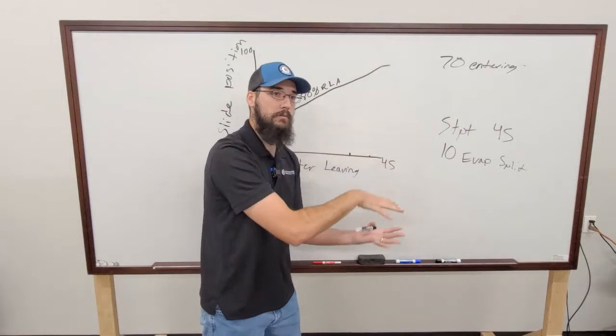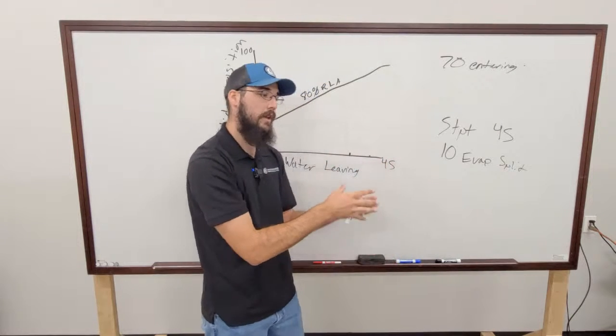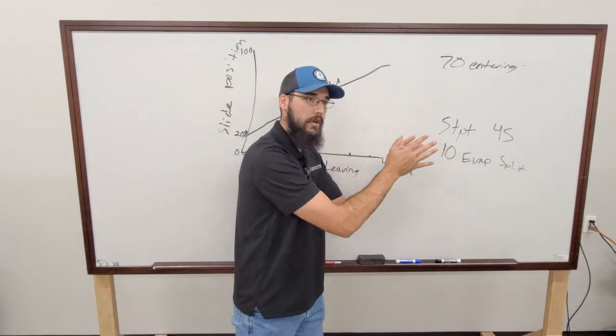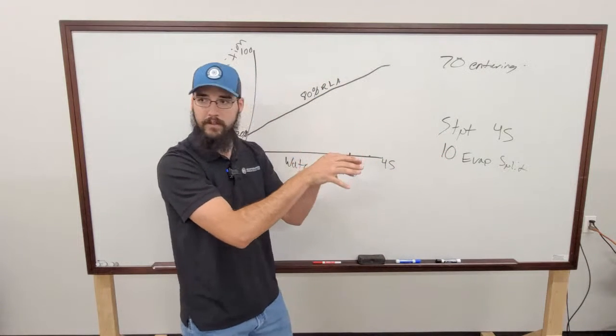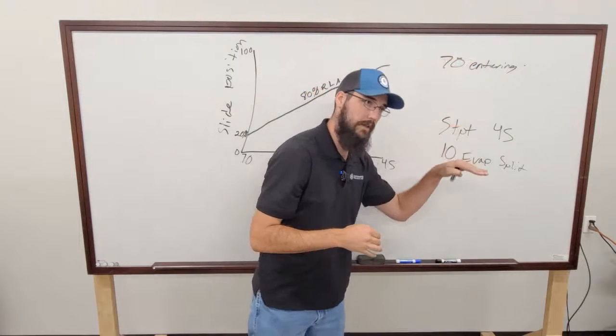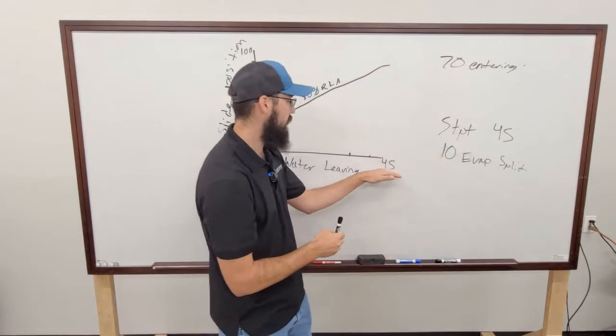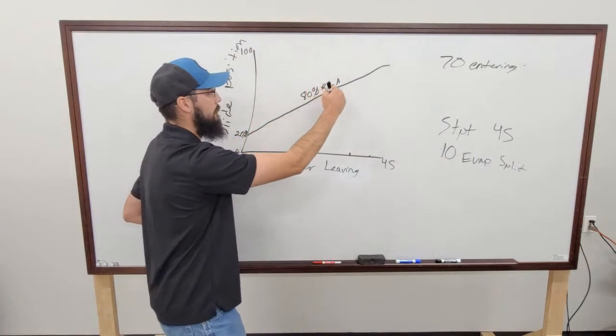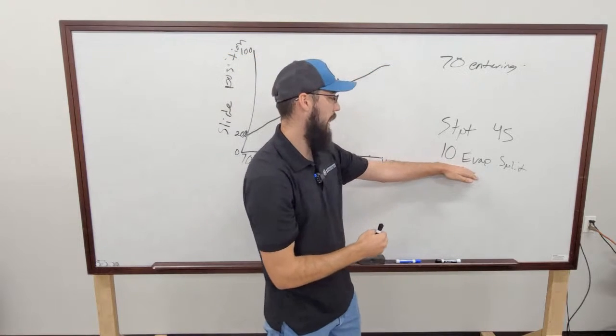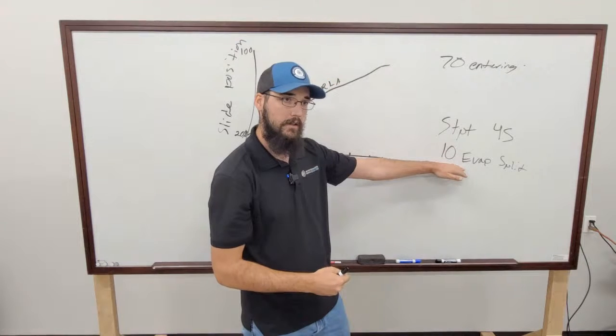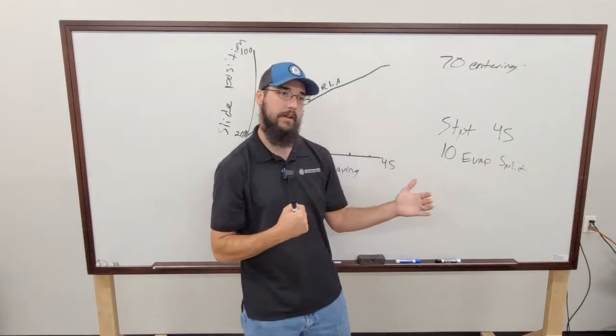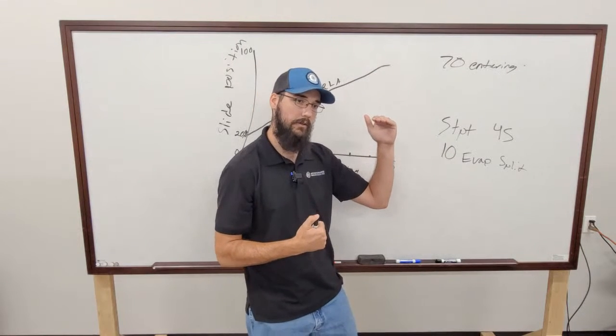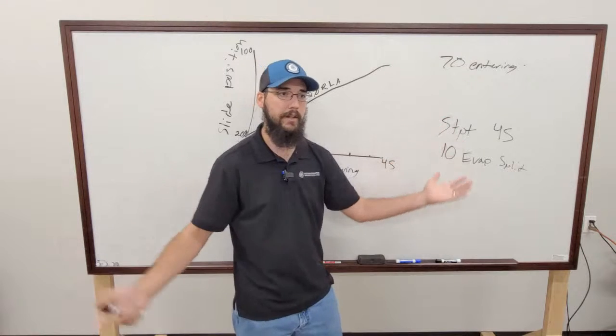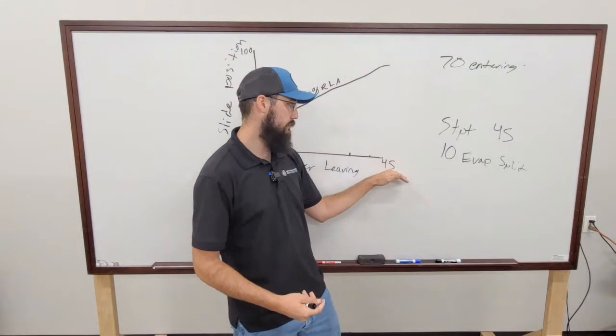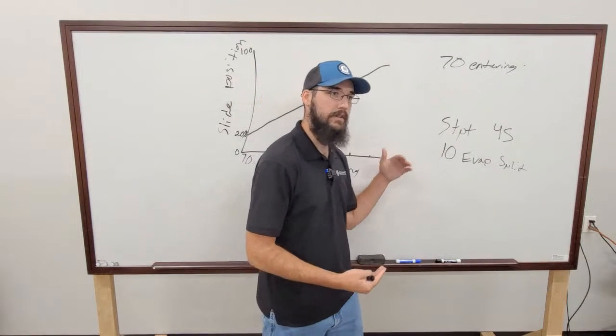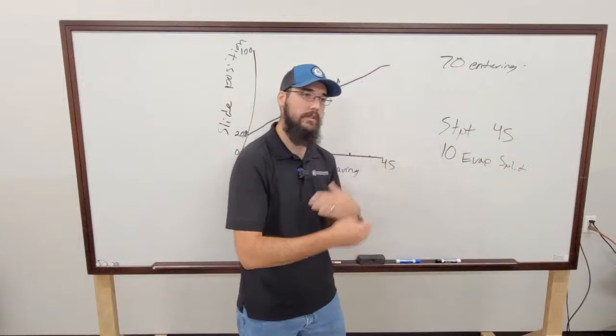Right. Well, yeah, the whole system load is decreasing. It's not so much that the saturation is decreasing, but the actual input BTUs on the evaporator are dropping. And as the input BTU is dropping, our output can come down a little bit too. And then once we get to the point where we no longer need to limit anything, and so we're no longer having an issue with a 10-degree split, and so we hit our 45 set point. Now we can start backing off on the staging, and say we get down to 53. Well, 53, which would be an 8-degree split across that evap, now that condenser has a much easier time keeping up with the load.